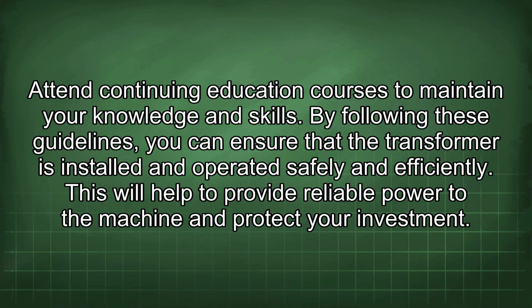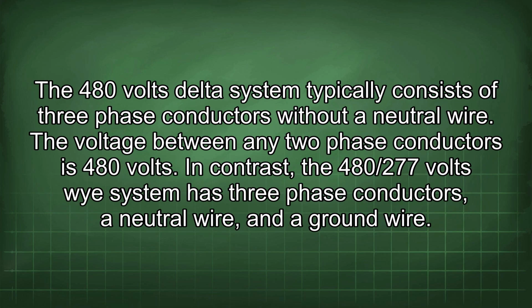By following these guidelines, you can ensure that the transformer is installed and operated safely and efficiently. This will help to provide reliable power to the machine and protect your investment. A 480 volts delta system typically consists of three-phase conductors without a neutral wire. The voltage between any two-phase conductors is 480 volts.